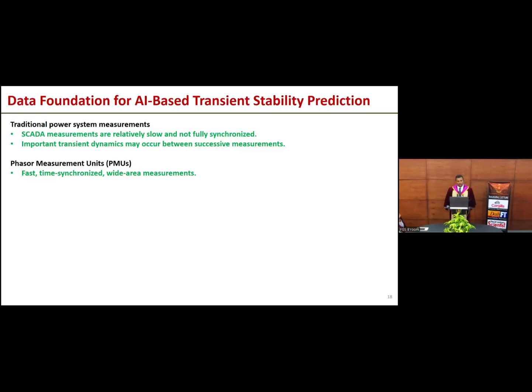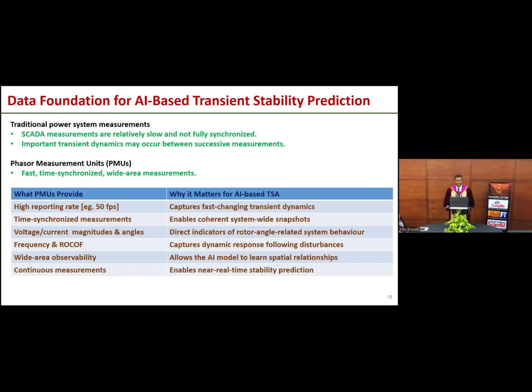So the solution in today's power systems is to go for phasor measurement units, which provide synchronized measurements. These devices communicate with satellites and provide time-synchronized synchrophasor measurements. Their sampling rate depends on how we do the settings; for a 50 Hertz network, it can even provide 50 samples per second.